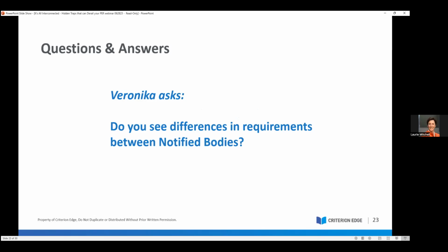In our MDR experience, which is what I will reference, we work with all of the clients whom we've written CERs for. Almost all of them ask us to assist them with answering the review questions as they come back. There are 3 rounds of review that a notified body will, if necessary, conduct until all questions that they've posed are answered.